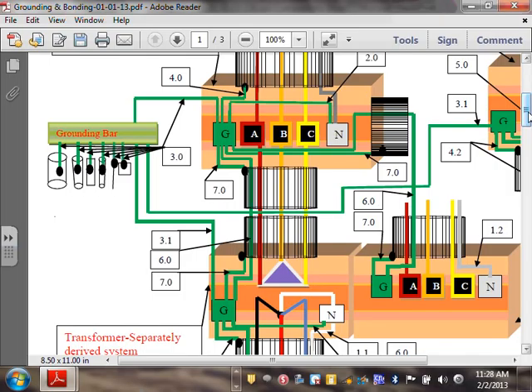And did we size number 6 and number 7? Yep, number 6, the equipment grounding conductor, will be sized based on the overcurrent protection device that protects that transformer right here. I think I have a size for that. And number 7 will be the same size as number 6. Equipment bonding jumper, supply side. Both of them, guys. Number 7 is equipment bonding jumper, supply side. I'm sorry, load side, because here's the circuit breaker, main. Everything down here, anywhere, is load side.